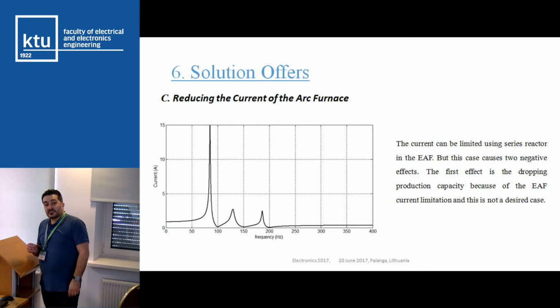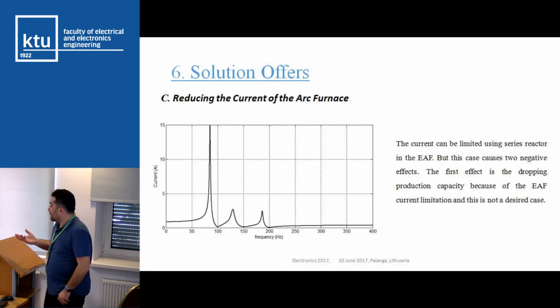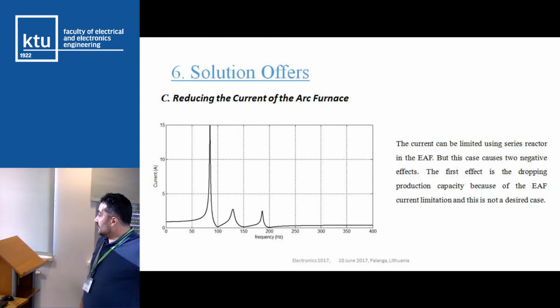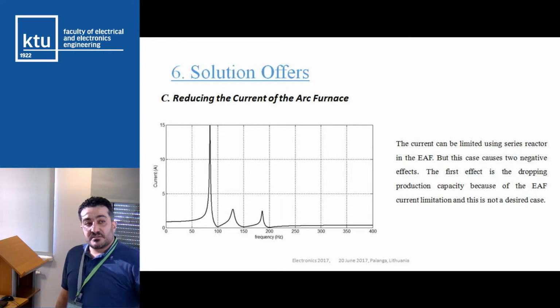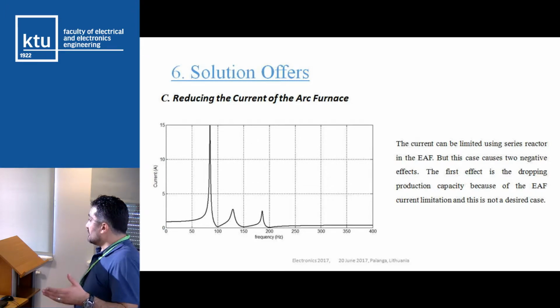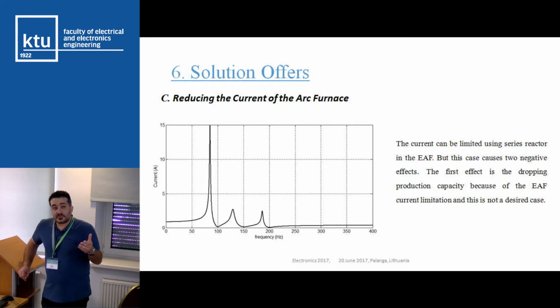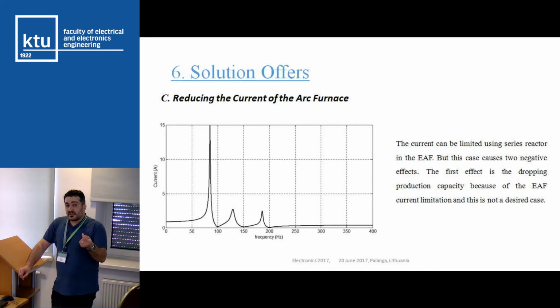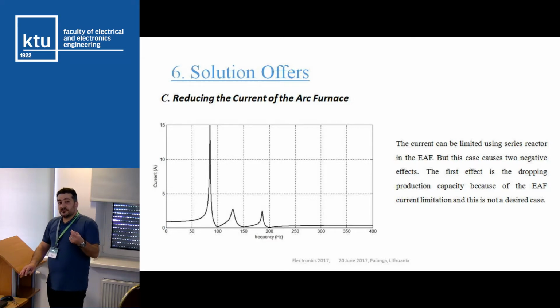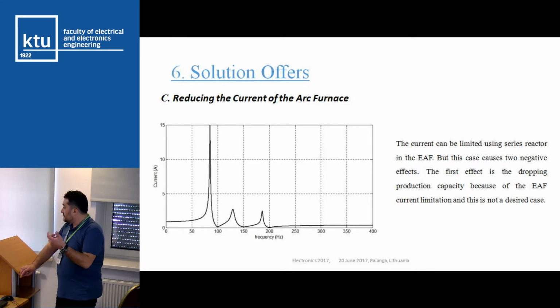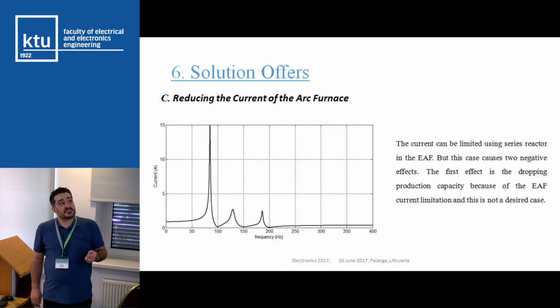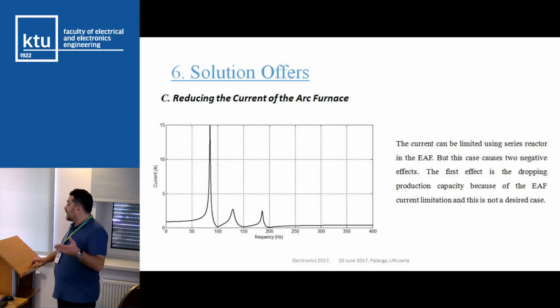It is a general application, but we are offering this application for big furnaces, because we investigated a 16 MVA furnace. If I reduce the arc current, firstly my furnace will not work very well, and production will be reduced. And second, for that I must add a series reactor to the system.